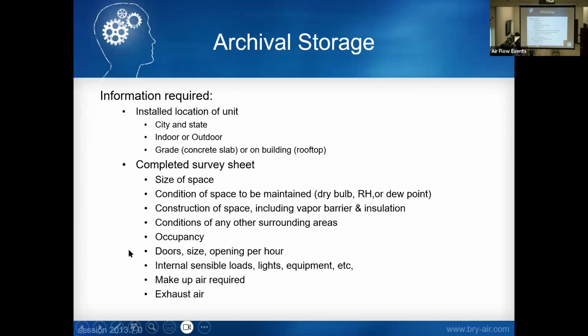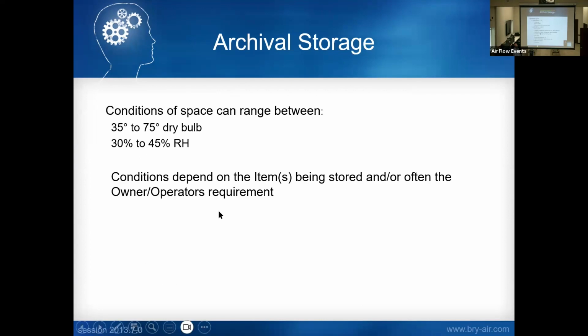Same kind of requirement. The only thing here that sometimes is added, and it's really not on the slide, sometimes you may need carbon filtration on the type of media you're storing in the environment. Typically we see about 35 to 75 degree and 30 to 45% RH. Again, it's really just dependent on the type of item you're storing.